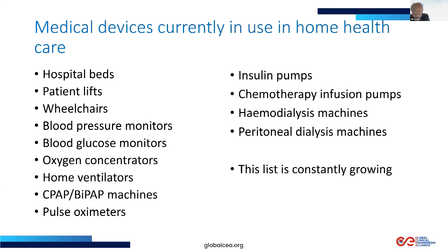They approached the work table. The joystick became jammed in the forward position, causing the wheelchair to push itself forward against the edge of the work table, causing the patient to suffocate, and they died. Again, a simple device, but with lethal consequences because the installation of the surrounding environment was inappropriate for the device. Next slide, please.